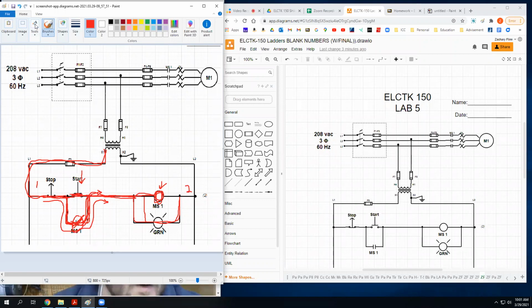Now if I let go of the start button and this opens back up, is current still flowing through that coil? Yes, it is. You see how that works? That's a holding contact or a seal-in contact. People call it different things. I typically call it a holding contact. But that's how a holding contact circuit works. I'm going to show you where that is on your motor starter, and then we're going to hook this up.